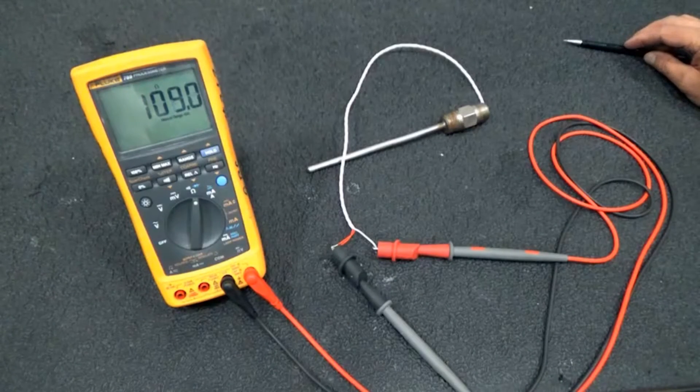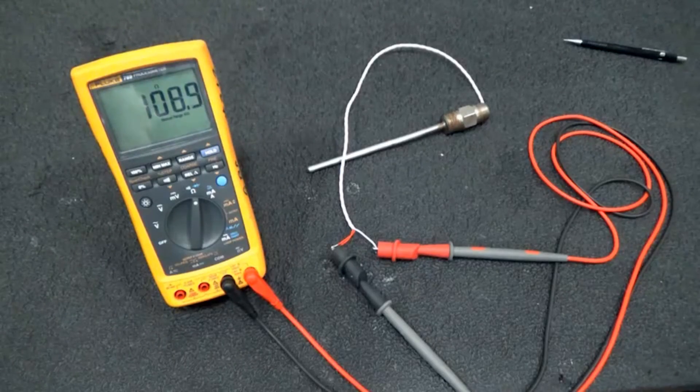We're reading 108.9 to 109 ohms. And if we wanted to, we could go look on a table, and I have one here, and we could say, all right, 109 ohms. That's about 73 degrees, and that makes perfect sense.